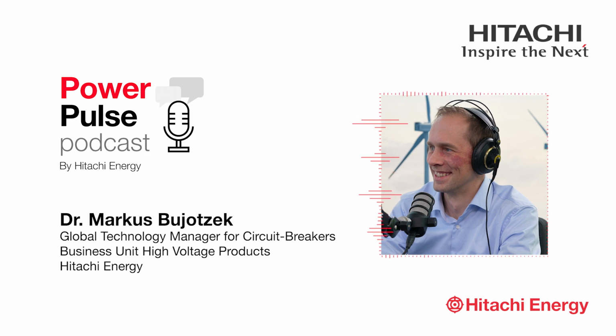So you have a high GWP, but beside that, it has excellent properties. It's super stable, it stays gaseous in the right range of our operating temperatures and pressures, and it has great insulation properties. It can withstand 3 times the withstand voltage of air, so you can make things much more compact. That's the purpose of gas-insulated switchgear. And if you put it at high pressure, even more so - you can make things very, very compact. It's non-poisonous and so on, so it has very nice properties.